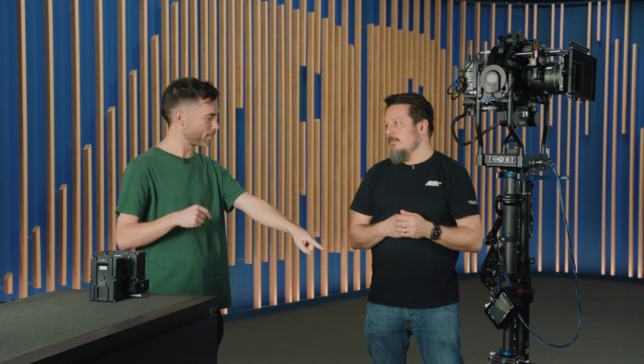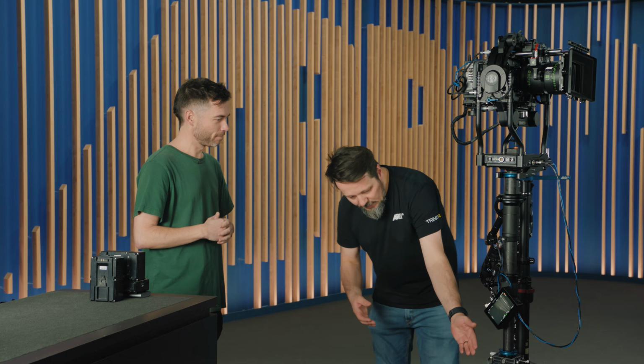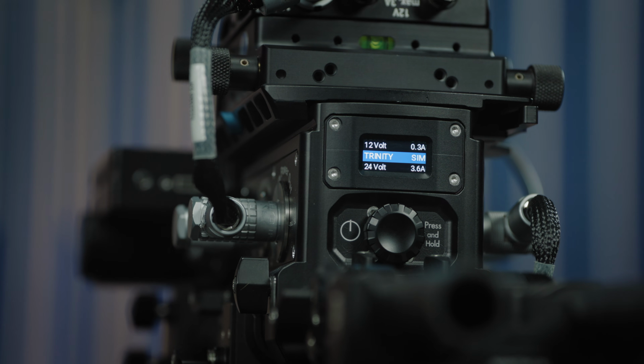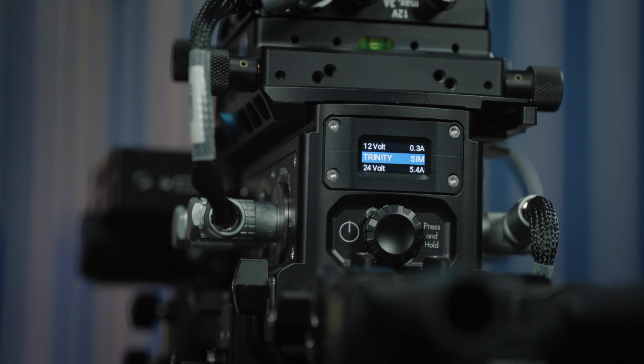There's also a little display at the bottom where you can always read what your system needs in power and what you're delivering to it. So you can see, okay, I might have a problem if the system needs 12 amps and I can only provide 10 amps. Then I know I have an issue and maybe need a third battery. So it's really good to check that display.